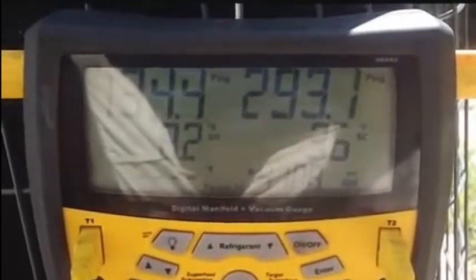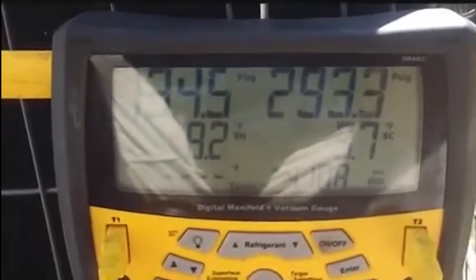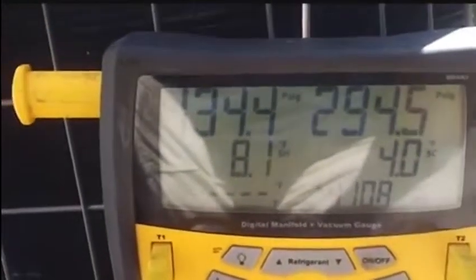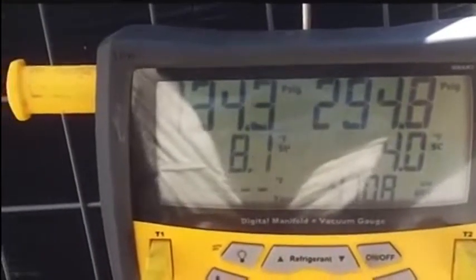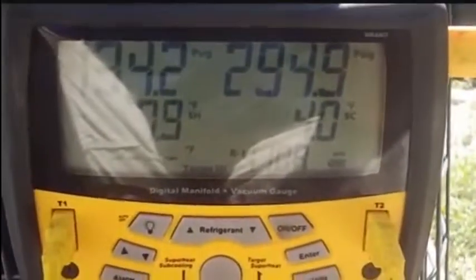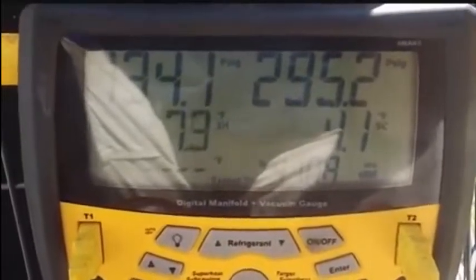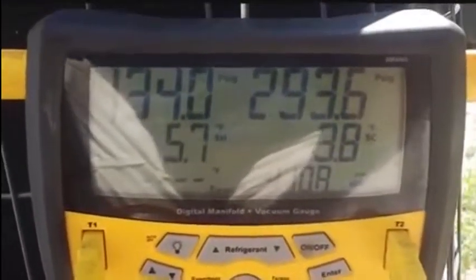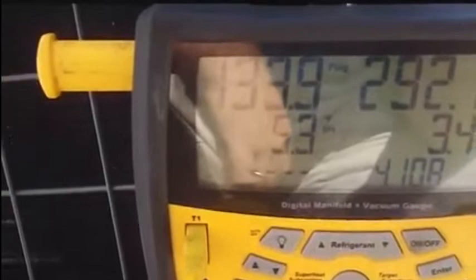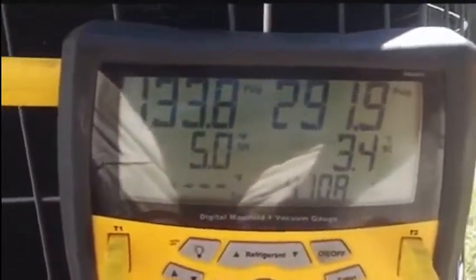All right, we've been running for just a few minutes. See our subcooling's still a little low, it's 3.5, it's been bouncing around. We'll let it go for about 10 more minutes. The superheat is right down there where we want it. There's a TXV on the indoor coil. It's actually the first trailer I've done with a TXV on the coil. I know that some of them do have TXVs, but not for me yet. So this is the first one of those.